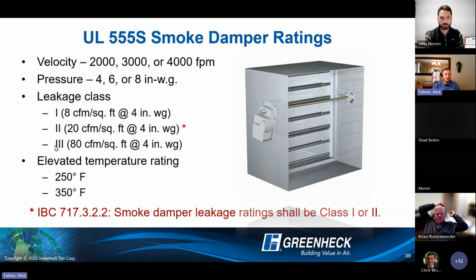But essentially from class 1 to class 2, you're going from 8 to 20. And then from class 1 to class 3, you're going from 8 to 80 allowable at that same test pressure. So just to give you an idea of the steps of class 1, 2, and 3 there.